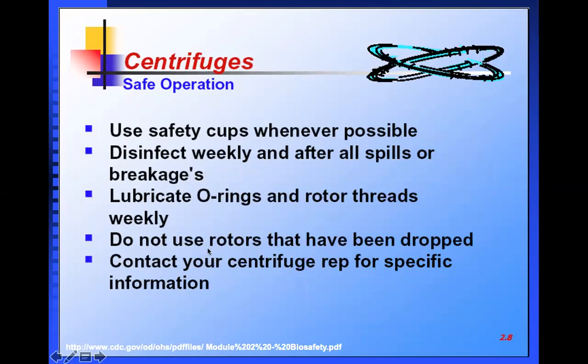Use safety cups whenever possible. Disinfect weekly or after all spills or breakages. Lubricate the O-ring or rotor threads, because if lubrication is not enough while the rotor is moving, friction can cause problems. Do not use rotors that have been dropped. Contact your centrifuge rep for specific information. Every centrifuge machine has a guideline or instruction guide, so you have to follow it.